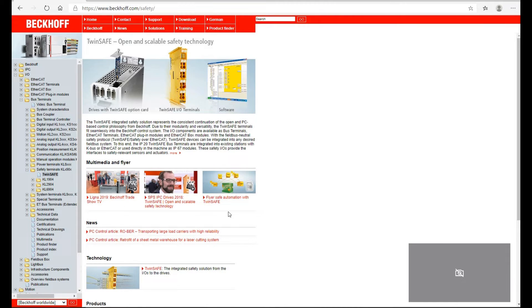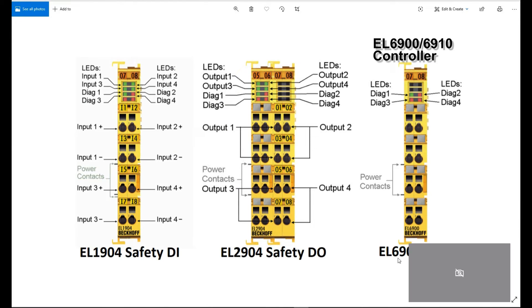Within the TwinSafe system, other than the software platform, from the hardware side there are three main cards. One is the controller EL6900 or EL6910. One is the safety input EL1904. And for the safety output, that is the EL2902 or EL2904. So it's very simple — just three main cards.